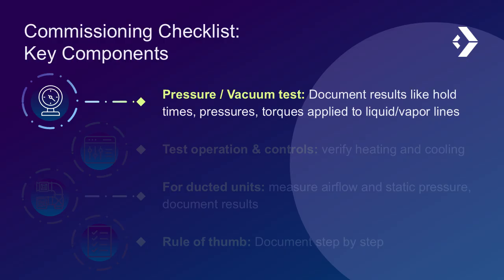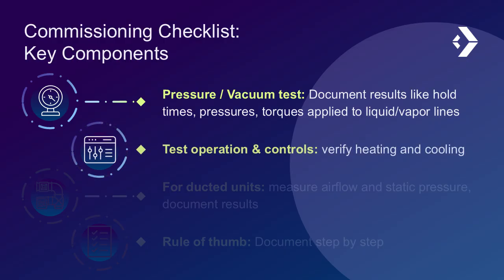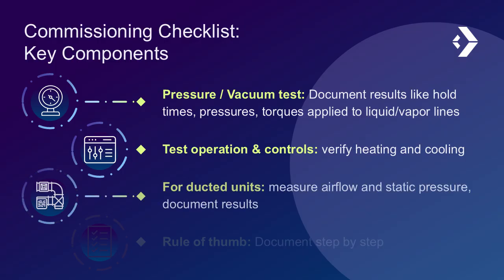Next, document the torque applied to the liquid and vapor lines and confirm that they meet manufacturer's torque specifications for that line thickness. Document that you used a refrigerant wand to sense leaks and that you fully protected each line with insulation and UV coating. Then test the operations and controls. Verify that both heating and cooling functions are working properly to ensure the system is ready for use.